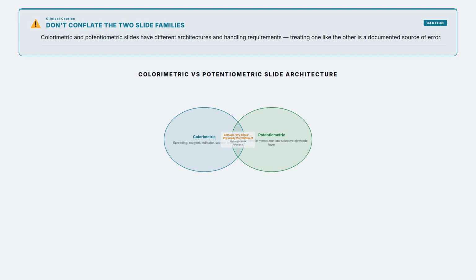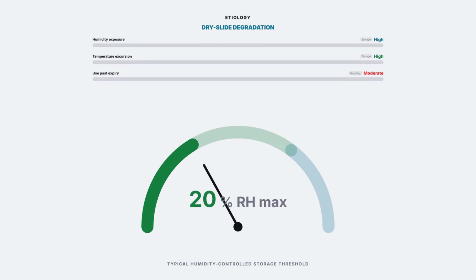Slide storage and handling deserve the same rigor as any reagent, because these are, fundamentally, dried reagents. Humidity exposure rehydrates and degrades the dried chemistry prematurely. Temperature excursions above the validated storage range accelerate enzyme denaturation within the reagent layer. And expired slides, even if they visually look intact, can carry meaningfully degraded reaction kinetics. Handling discipline that protects slide integrity.